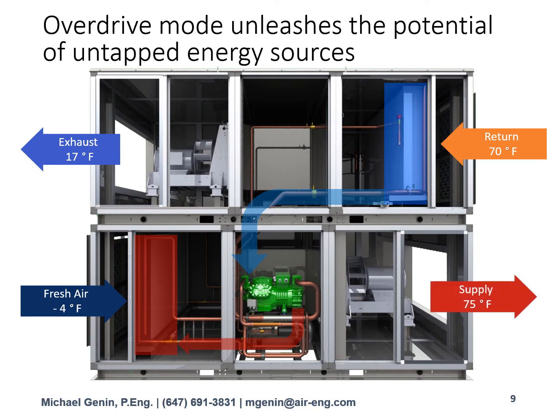Another advantage of heat recovery is overdrive mode. And I've chosen a supply condition here of 75 Fahrenheit. I'm running the refrigeration system a little warmer than normal. And what that does is it offloads the heat from your central plant and puts it onto your ventilation unit. So as we discussed, the fresh air or active heat recovery has a COP of about 7 seasonally.